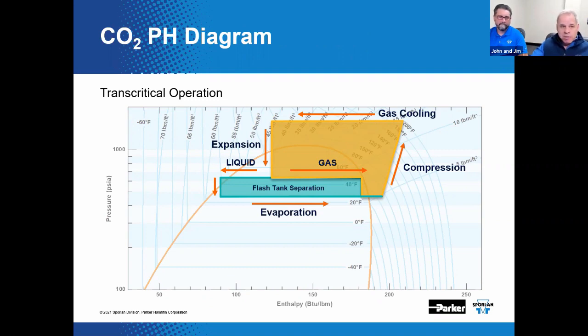Remember, at temperatures above 87.9 degrees Fahrenheit, CO2 doesn't like to condense. That's right. All you can do is some form of sensible cooling of the hot gas and no latent heat transfer at this point. The really smart engineers have a fancy name for this process. You know what it is, John? Yeah, they actually call it gas cooling, which is very clever. Yeah, I would have never thought of that.